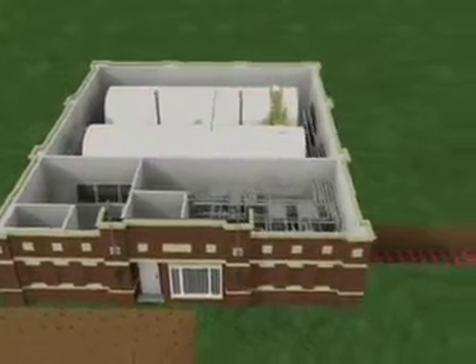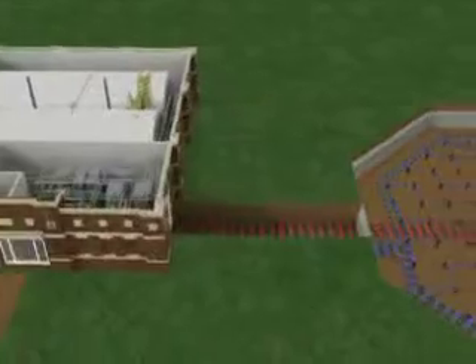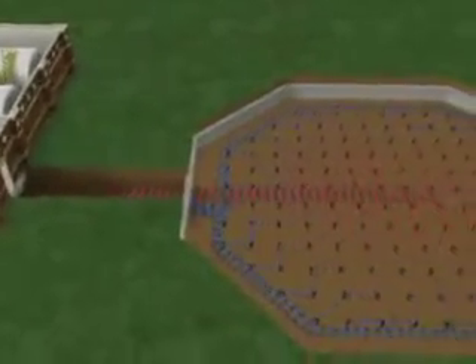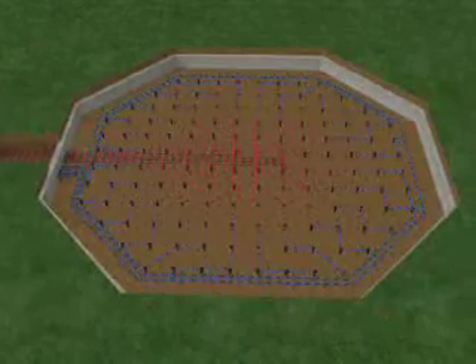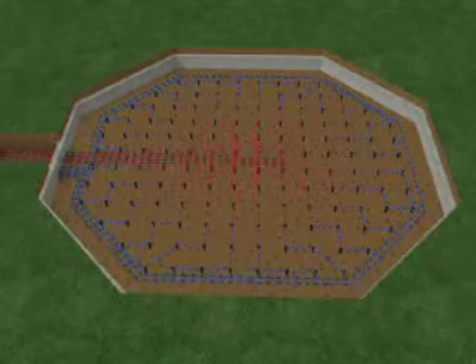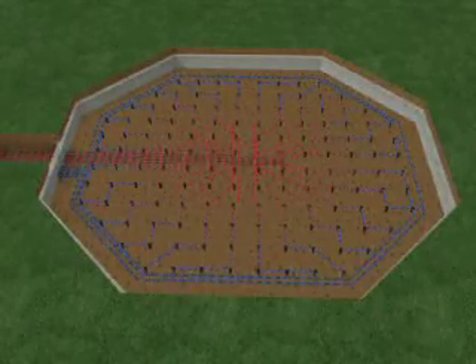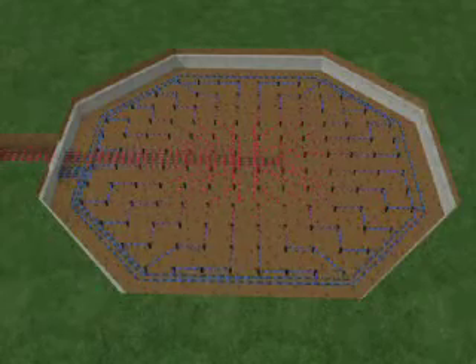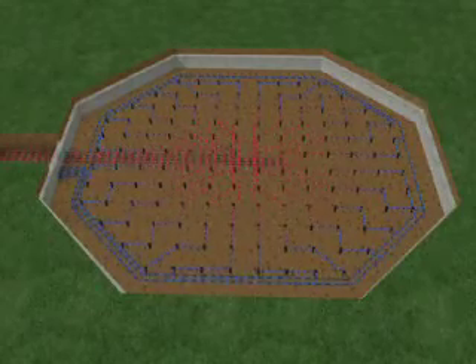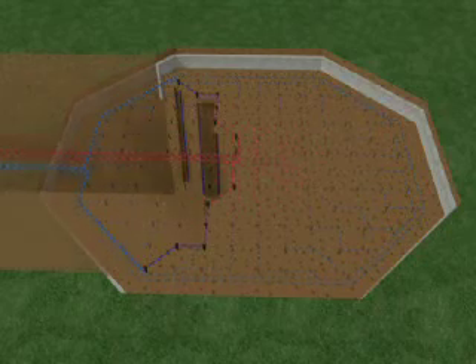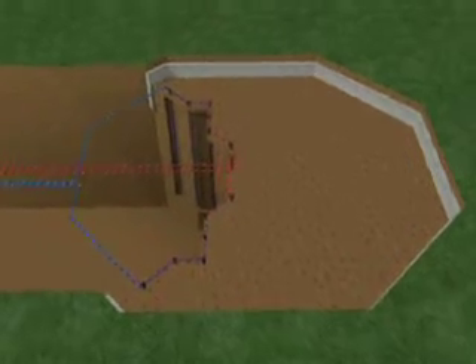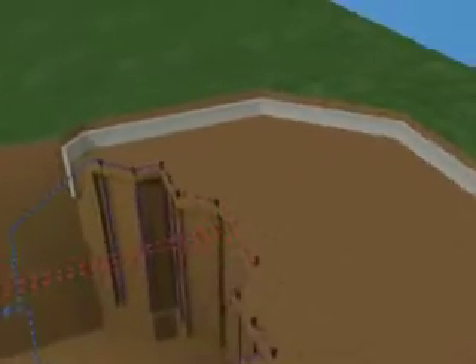From the short-term storage tank, the heated water is distributed to the borehole thermal energy storage system. Consisting of 144 holes that stretch 37 meters below the ground and cover an area 35 meters in diameter, the borehole system is where the summer's heat is stored for use in the wintertime. As the heated water travels through the pipework, heat is transferred to the surrounding earth. The temperature of the earth will reach 80 degrees Celsius by the end of each summer.